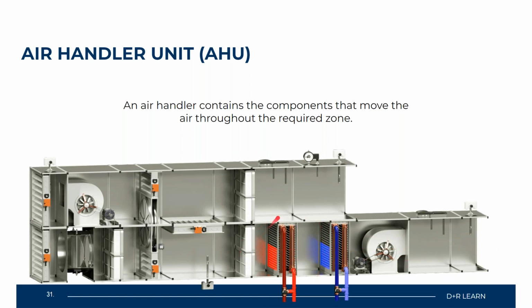So you can see here, designated by some colors, we have red for heating and blue for cooling. When you are in heating mode, there is no cooling. That is offline. What's happening here is hot water is transferred from your boiler system to this coil. When this fan comes online, it's going to draw the air across the coil, making that air a certain temperature as it's sent out to the different spaces where it's required.